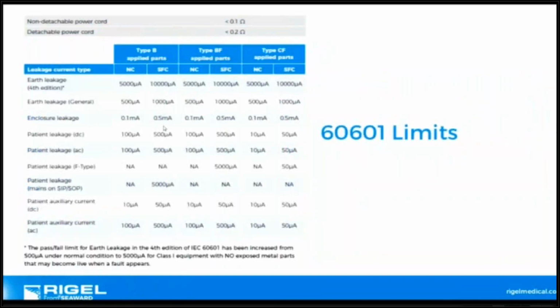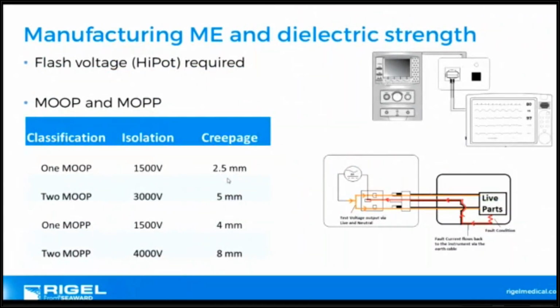And these are some of the safe limits for your 60601. Looks very complex. There's a lot of information there. Most electrical safety analyzers, like the 288 in particular, you don't really need to. It's nice to have the knowledge to be informed of safe currents, but with the 288, as long as you've identified the device, all of these currents are pre-programmed and will give you a failure if they're above the pass-fail thresholds.